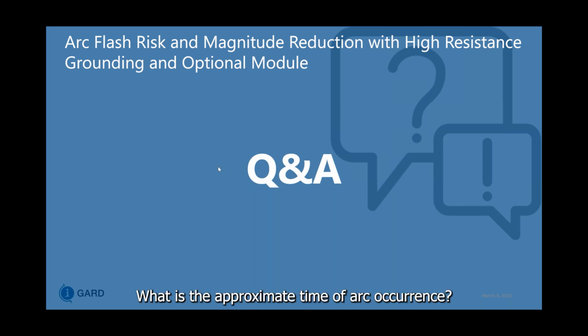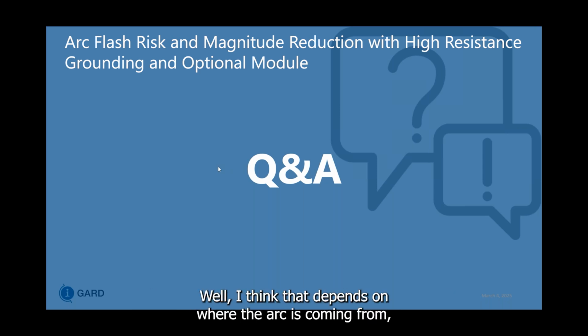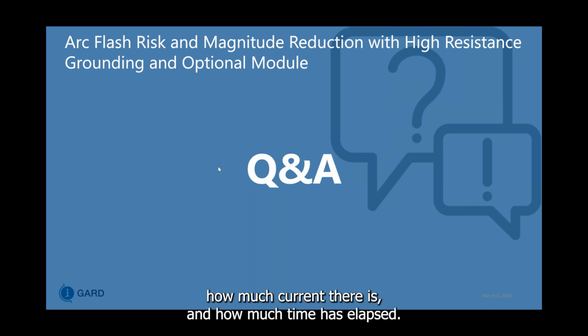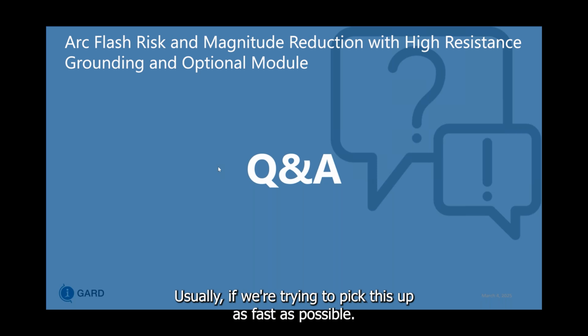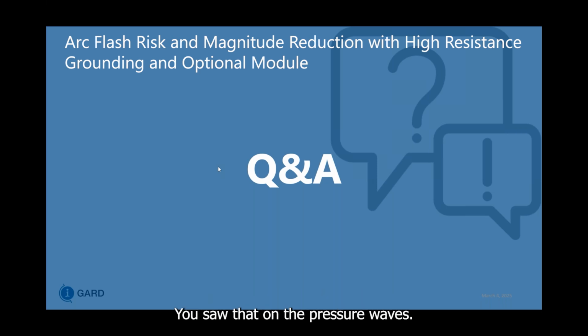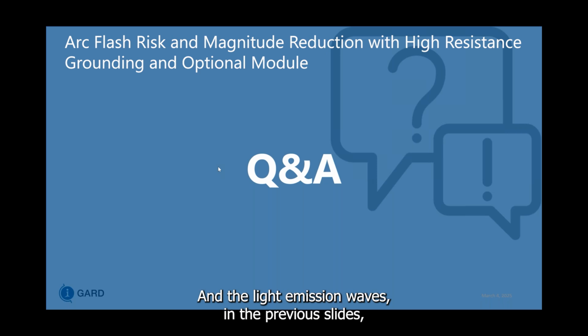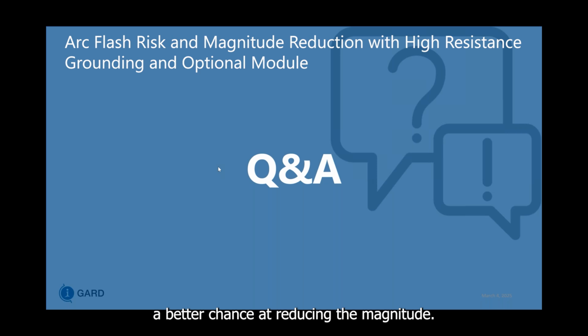What is the approximate time of an arc occurrence? Well, I think that depends on where the arc is coming from, how much current there is, and how much time has elapsed. Usually, if we're trying to pick this up as fast as possible, you saw that on the pressure waves and the light emission waves in the previous slides, we see that it's happening in just a few milliseconds.